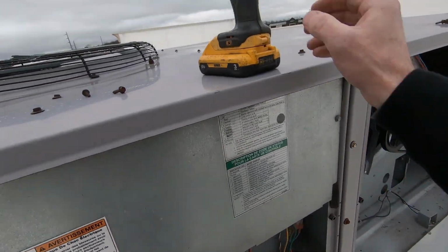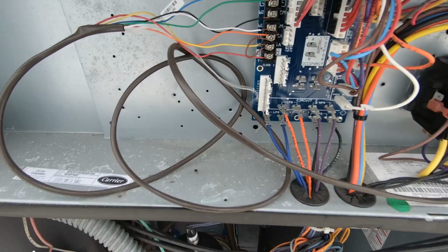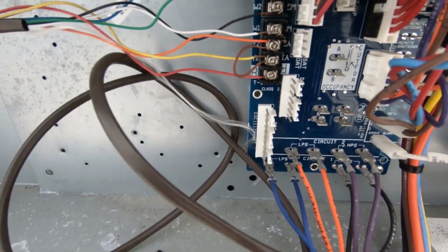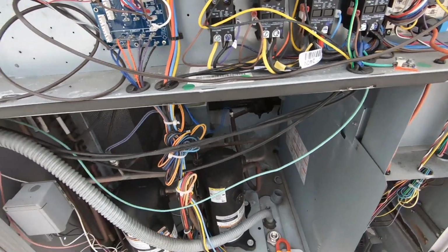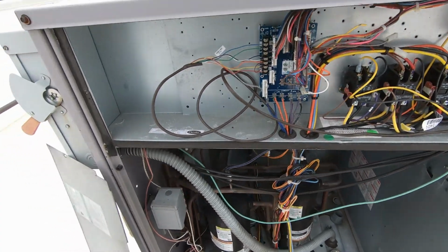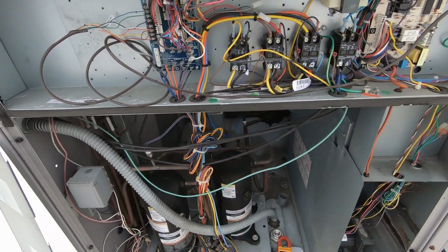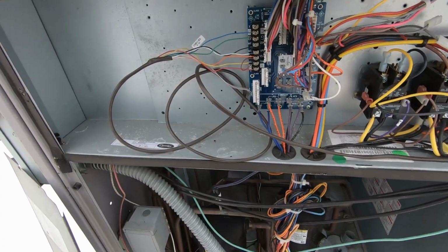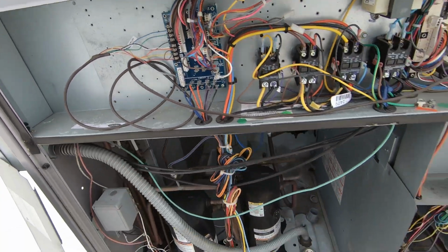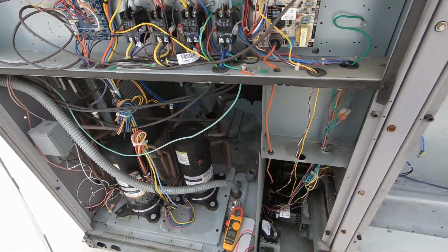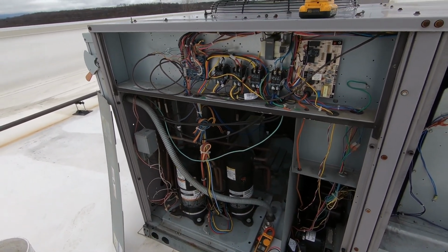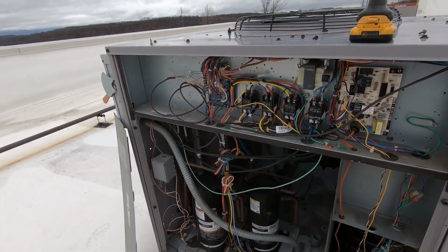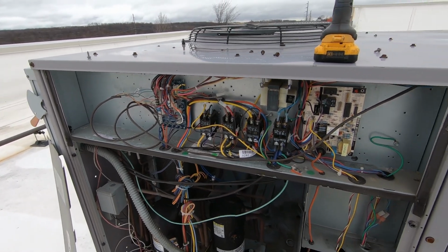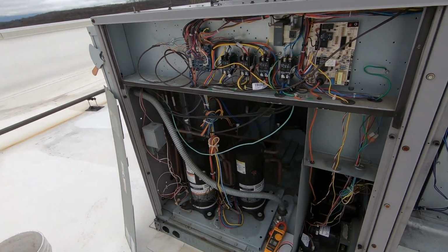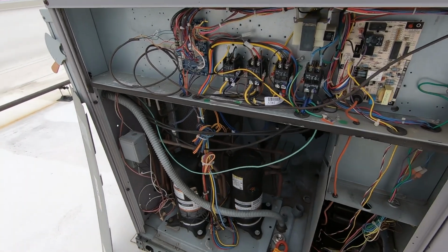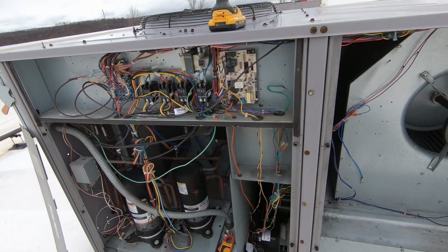This one's in a lot better shape than the other one is. All right, Y1 and Y2 are jumped. So clearly something's going on with the AC. Maybe that compressor is locked up, I don't know. But somebody jumped out Y1, Y2, pulled the plug on first stage compressor. Probably so the contactor would pull in, the fan would continue to run while second stage acted like first stage compressor. Possibly. Like I said, I'm not digging into air conditioning today.